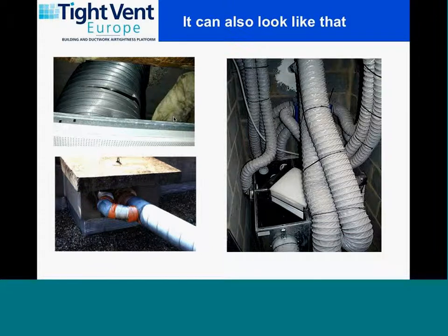So basically, air that is going into the ceiling is lost, and in that case, it was a system that was also used for preheating the air. So, well, there's obviously a considerable amount of energy that is lost directly in the ceiling. Then there is this sort of art piece on the right-hand side, which obviously is not optimal as far as pressure drops are concerned. Well, it's not very nice either, I guess.